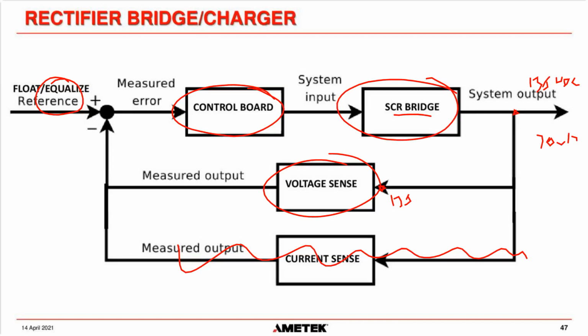But if our AC input into the system goes down, our DC voltage is going to go down. So our voltage sense circuit says, something is causing my voltage to go down, let's say to 130 volts. It sends that error signal, and the control board says I need to turn my SCRs on earlier in their phase cycle and get more voltage to the output. The sensing circuit keeps doing that until it gets to 135 volts, and then it goes back to equilibrium.